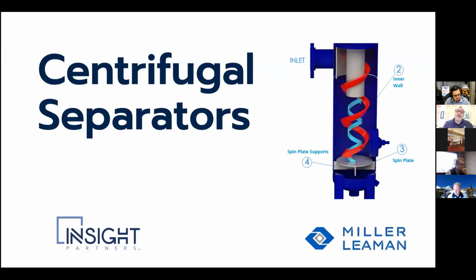On a cooling tower, only around 10% of the particles have that specific gravity of 2.2 or larger. It's not going to remove any of the cottonwood seed, the pollen, the organic matter, or anything like that. It's going to spin right through. Have we used them? We have, but we use them as pre-filtration to heavy loading of dirt, and then the polishing would be a turbo disc filter. Remember, you're only taking 10% of the water. If you want to remove 10, 20% of the particulate, centrifugal separation will do a good job removing the heavy particulate.